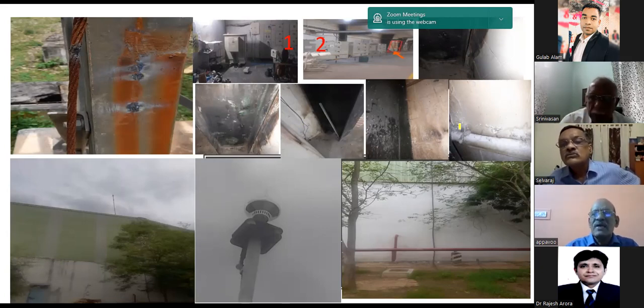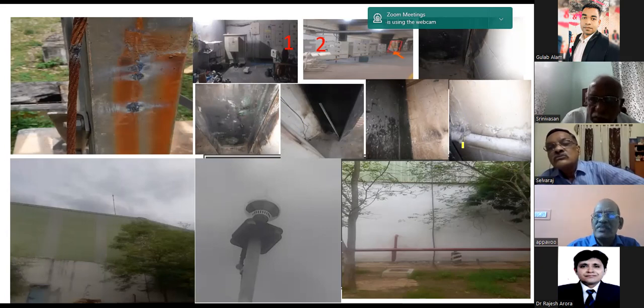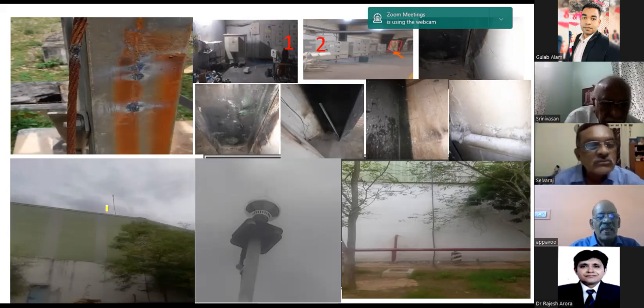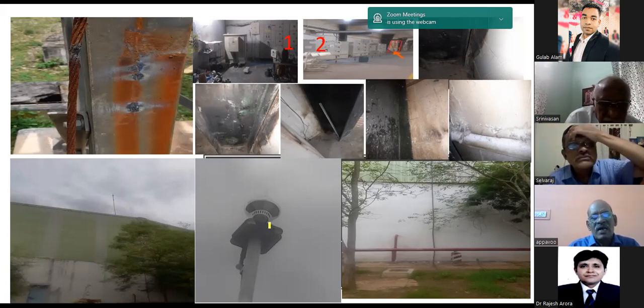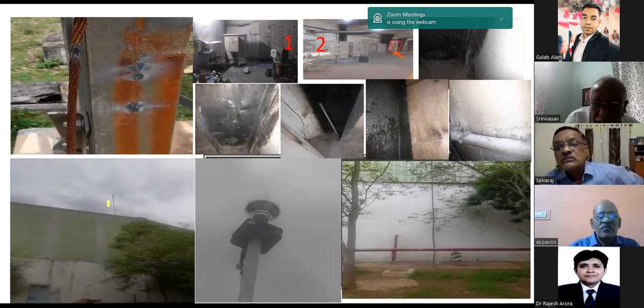Then you can see a PVC conduit atop the beam that was running, penetrating between the steel beam and the adjacent wall, which is penetrating because of the gap. And you can see a lightning mast using early streamer emission at a corner of the building. And you can see an insulator also fixed to the ESE lightning. And a single down conductor from this top. This is another single down conductor connected to the earth.